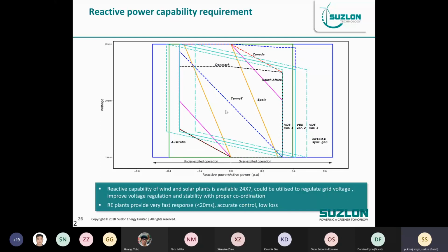Another requirement is reactive power. Although this is known, the reactive power requirements at the park level are quite different from one country to another. This requirement can be met by the wind turbines and some additional equipment, but the problem is that with every change there is huge investment cost at the park level. So if somebody has to meet South Africa's requirements and then move to, let's say, ENTSO-E's, here you can see the square - the reactive power from 0% to 100% - you have to fulfill the requirements.